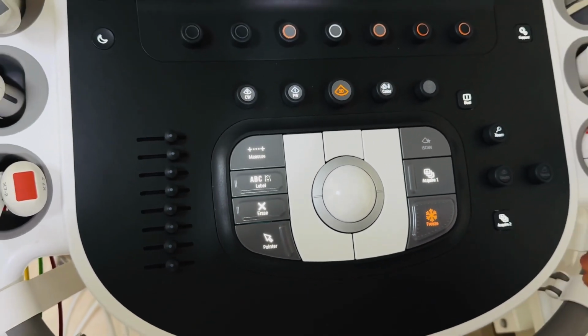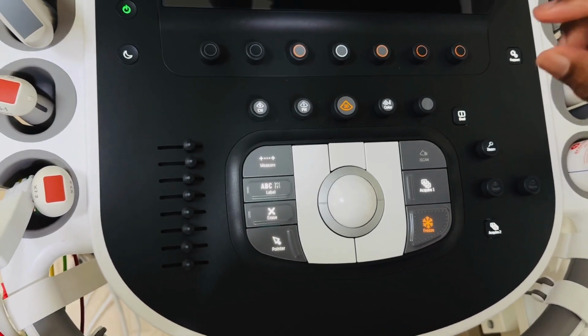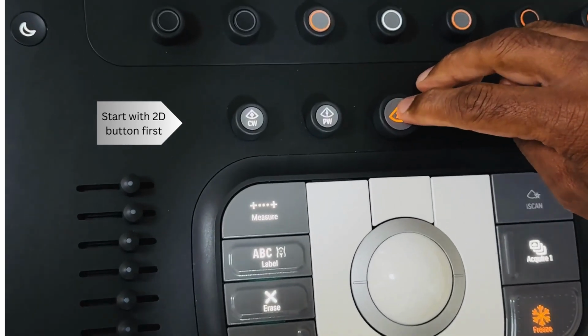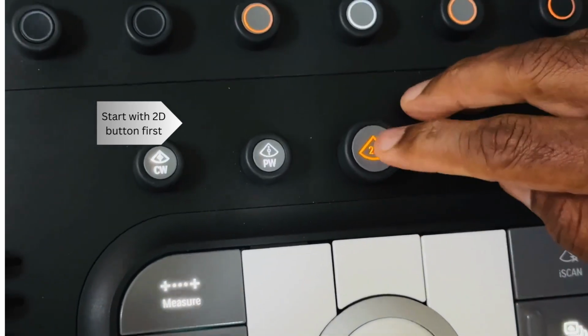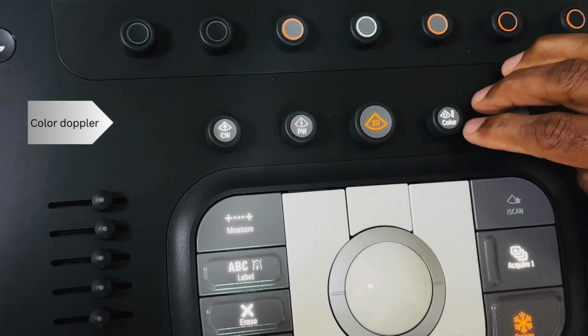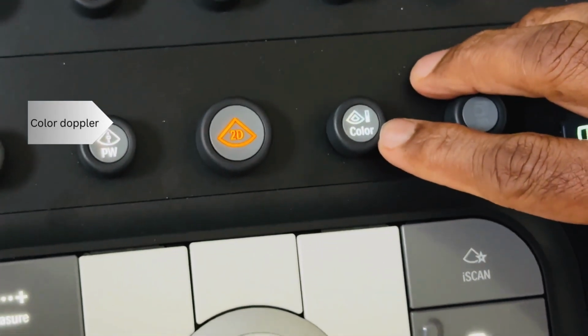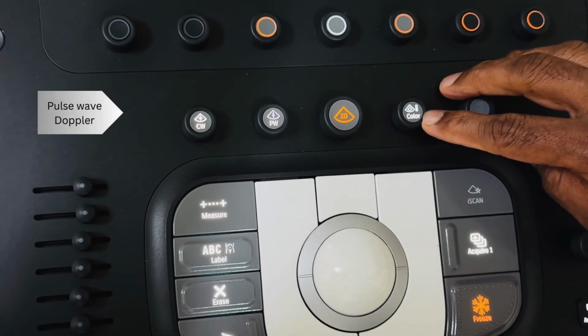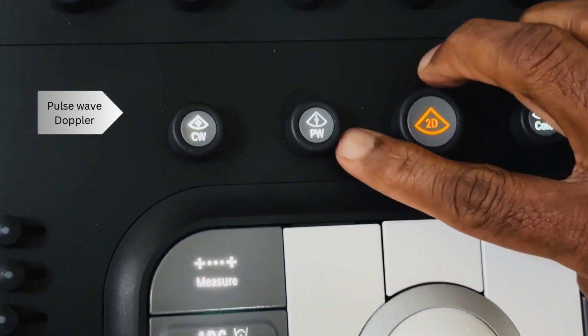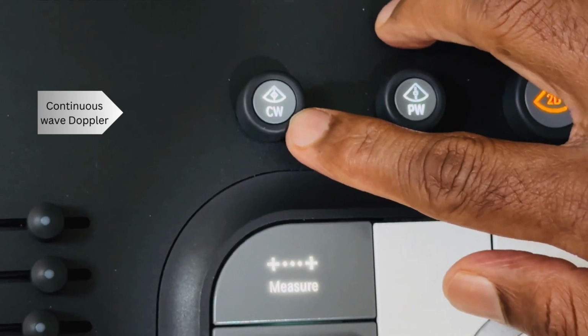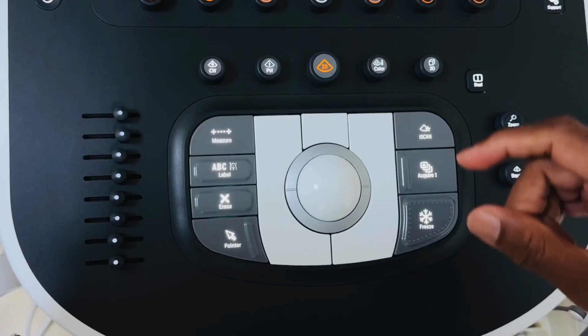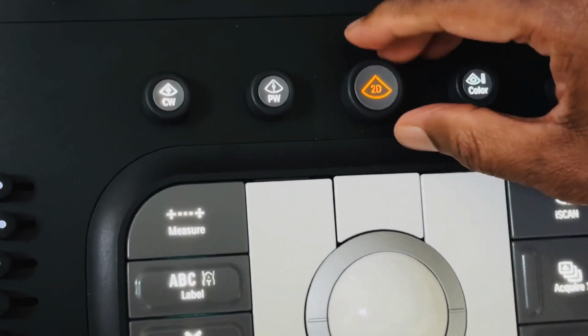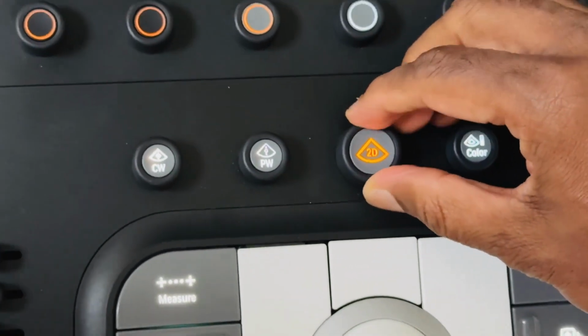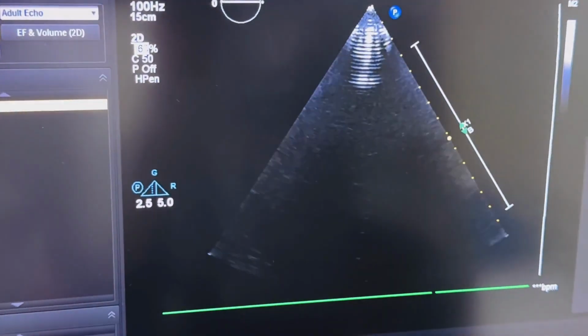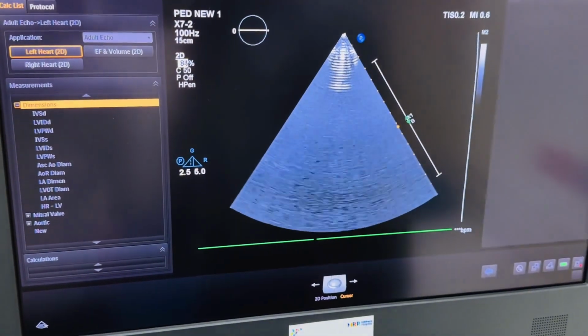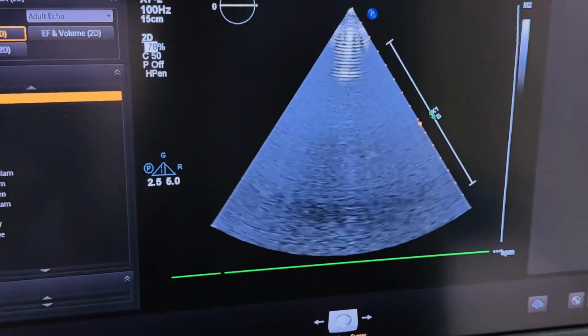Now when you're scanning, for any scan or ultrasound you always start with 2D first. So 2D or the B mode will be done by the 2D function. Then you put the color on, which will tell you the direction of the flow. And then if you want to measure the velocity of that flow, you put either pulse wave Doppler PW or continuous wave Doppler CW. So generally many machines will have a gain function. In this particular machine, the gain function is actually fixed on this 2D knob. You increase or decrease the gain on the same knob. As you can see, this is very bright and then decreasing it's very dark.